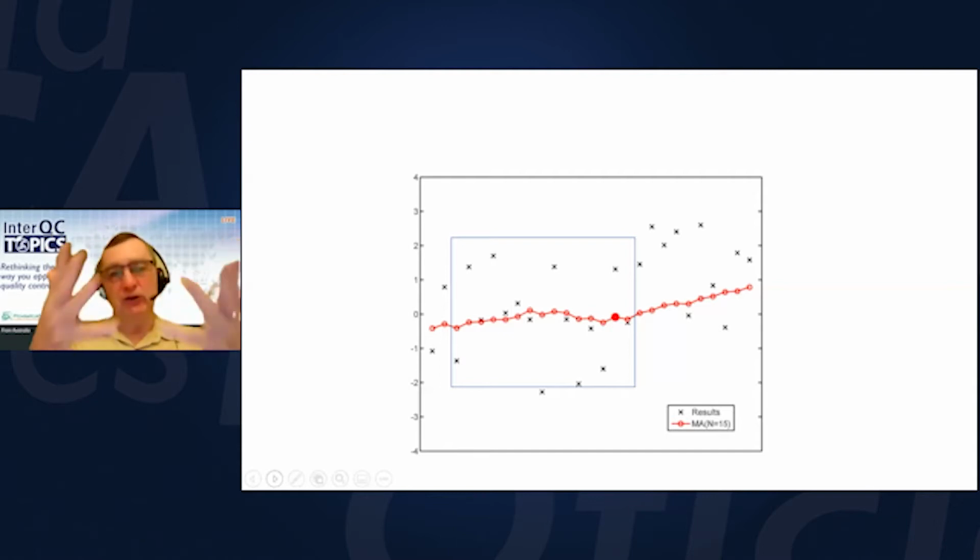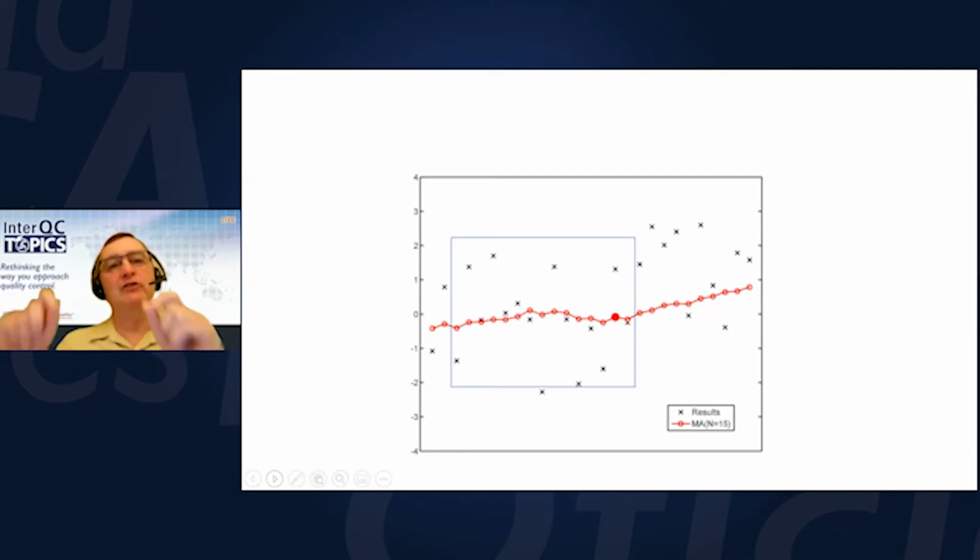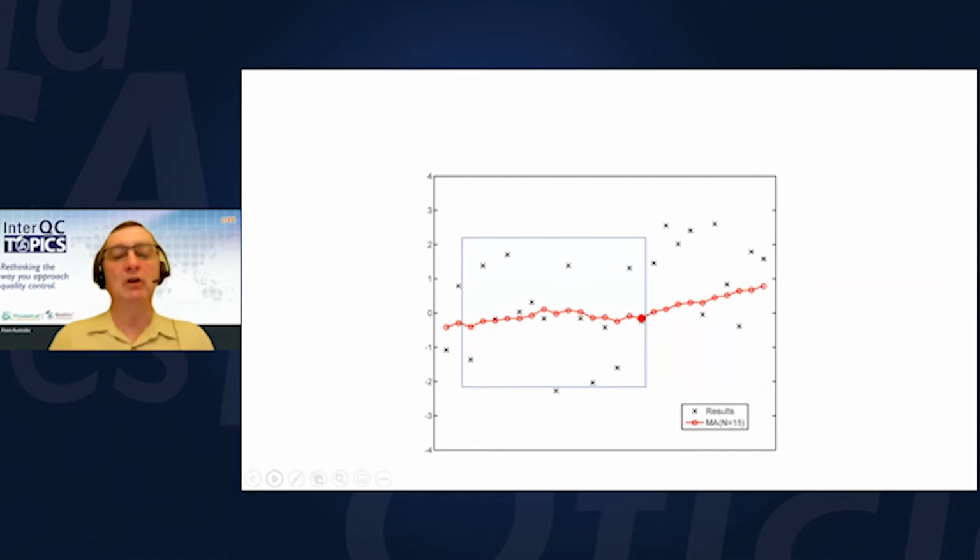And as you can understand, the point of this exercise is that if you've got patients who normally have results of sodium, say 139 to 142, if there's a shift in the bias because of something to do with the assay, calibration or reagents, and the bias moves, as you keep taking your averages, your average after 15 samples will start to move up. And that way you can detect this shift. So that's all patient-based moving average is about. You just keep moving this point along, taking the new average, and that becomes your new point.